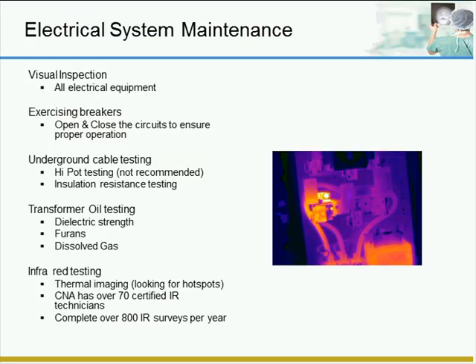Thermal imaging. IR testing identifies hotspots in systems due to elevated temperatures. Common causes for elevated temperatures would include corroded connections, loose connections, overloaded circuits, faulty equipment. The picture above here is an infrared picture, and it shows a loose connection in a disconnection panel. This condition here could result in arcing, fire, or potential downstream equipment failure.